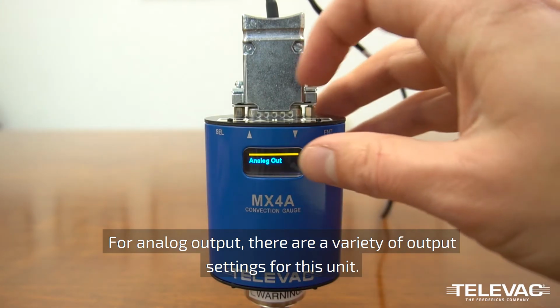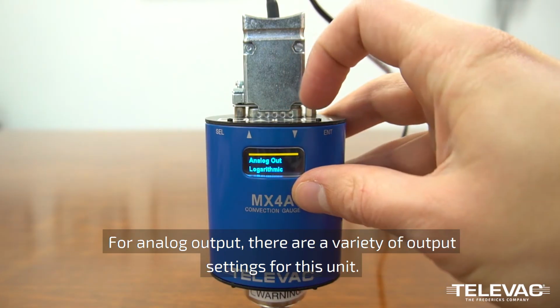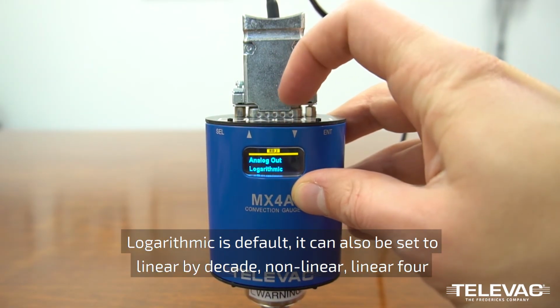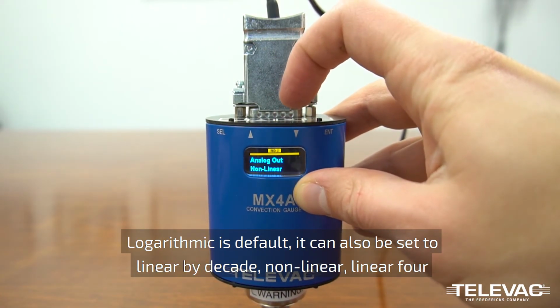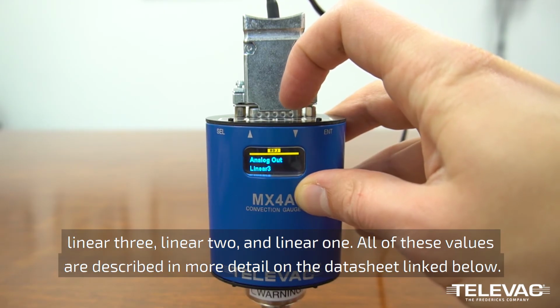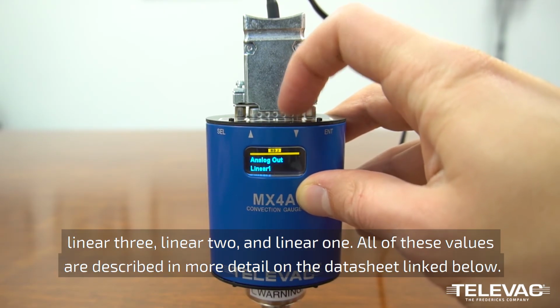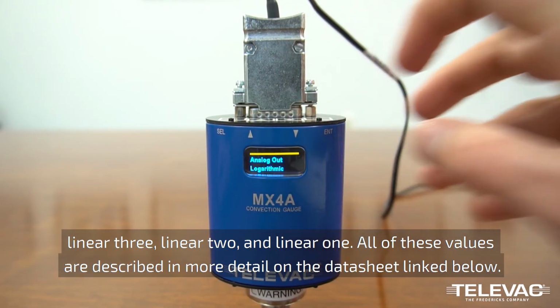For analog output, there are a variety of output settings for this unit. Logarithmic is default. It can also be set to linear by decade, nonlinear, linear 4, linear 3, linear 2, and linear 1. All of these values are described in more detail on the datasheet linked below.